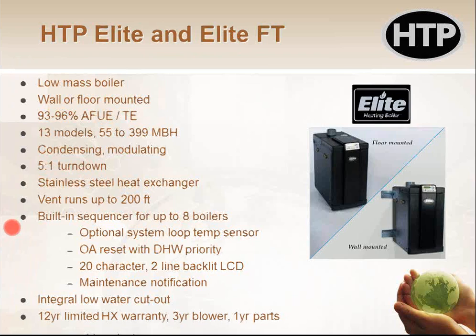The big brother to that Contender is the Elite boiler. These guys go from 55,000 BTUs up to 399. By the way, you'll see a lot of boilers that are at 299, 399 type sizes. That's because at 300 and 400 they go into different category ratings for different reasons, right? So at 300 it becomes a commercial boiler as far as AHRI is concerned, so it has to get rated commercially. 299 is still a residential boiler, regardless of the kind of building you install it in. And then usually at 400, some other rules kick in with the fire marshals and things like that. So you'll see a lot of 199, 299, 399 sizes for that reason.